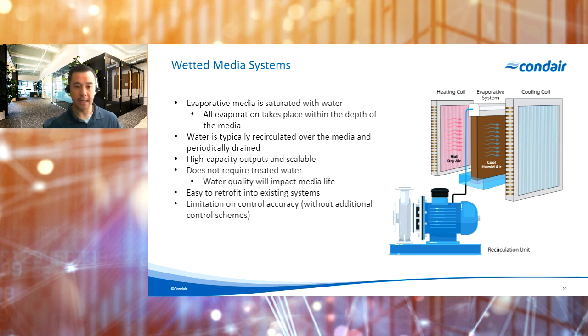Now, a consideration that you should keep in mind here if you're looking at or considering a wetted media system is on the controllability side of things. Because we're pumping water to the top of the media, we're relying on gravity to pull that water through the pad itself or through the media itself. That media is going to take time to fully saturate and hit maximum performance, as well as once we hit that point, it's going to take some time for that media to dry out as well. So typically with a wetted media system, it is going to be a bit slower to respond to changes in demand. So if you do have requirements for tighter control, tighter temperature or humidity, leaving air conditions after this section, you may want to look at implementing different control strategies, so bypass control or even face and bypass control if you do need those tighter conditions.